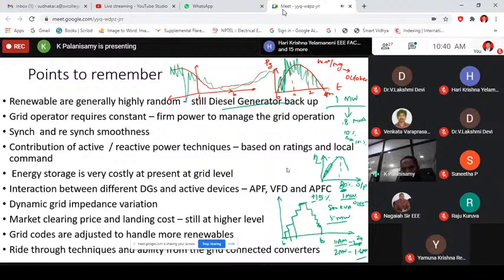That kind of command you will get from the microgrid central or master operator. So in microgrid operation also that will be an issue. For example, if the microgrid is a wide area, a few square kilometers, it is very difficult to track the command from the central microgrid operator. So that is why most of the power converters, the renewable energy converters, based on the local variable, will derive the control parameters. I repeat, most of the power converters, let it be solar or wind or whatever renewable converters, will derive the control variable from the local variable.